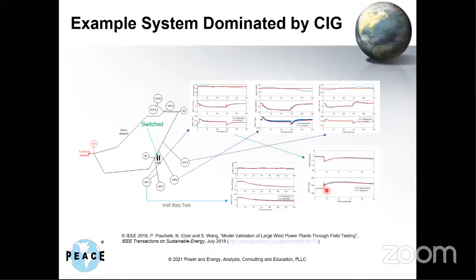After doing that for all the plants, we switched a large capacitor on the transmission system and looked at the response of each plant, and everything matched quite nicely. That showed we got a good match for each plant. Then we built a model of the whole system and switched the cap, and everything matched without touching any of the parameters—good verification. And if you zoom in, even at the very short time interval level, where the inverter-level controls are really kicking in, you still get a pretty good response match.